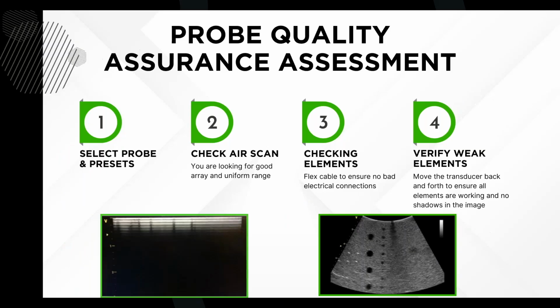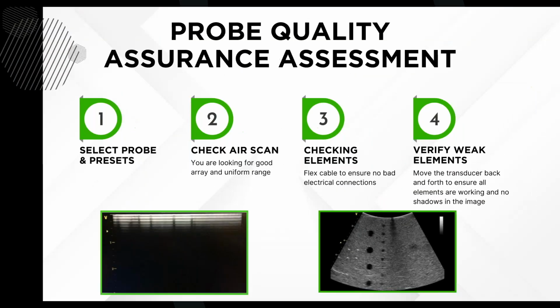All right, let's go back here. So, the other thing I would check in transducers, we talked about select probes, presets. We went over checking an air scan. I'll show you an example of an air scan on this particular system. Back here. Oh, wait for that one to go over there. Go back to 2. So when we're checking the air scan, you're looking for good array and uniform range. You want to flex the cable to ensure there are no bad electronic connections. And you want to move the transducer back and forth to ensure all elements are working and there are no shadows in the image.